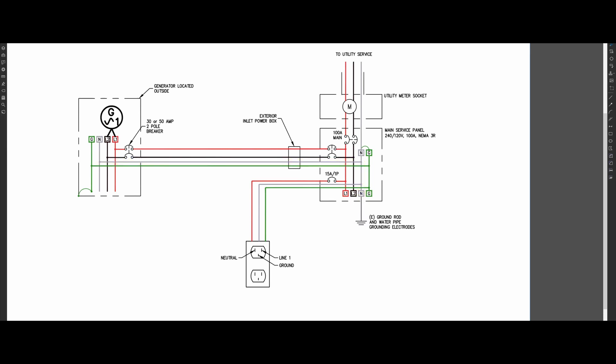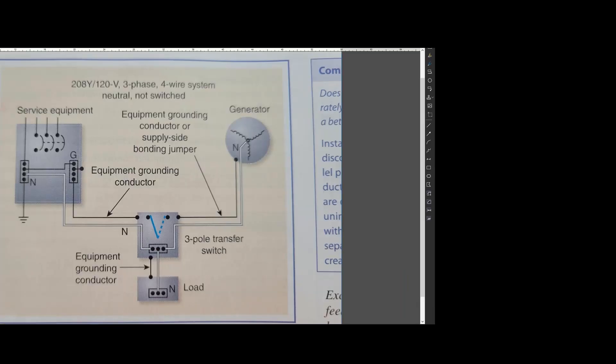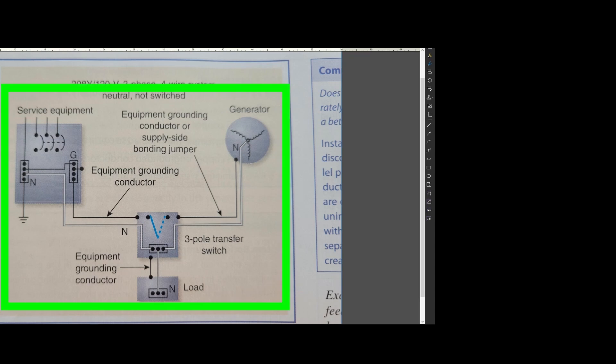If you shut off the generator circuit breaker here, the circuit breaker only opens line one and line two. The neutral wire is continuous at all times. Because this neutral wire is continuous, this entire setup is considered as one single system.